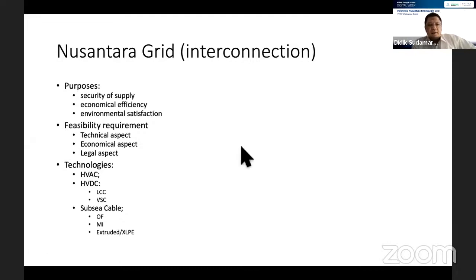The technology we have to focus on regarding this interconnection available in our system is about HVAC, high voltage AC current, and then HVDC. In HVDC we have two types, LCC and VSC, which I will explain later. For subsea cable, there are mainly two types: oil-filled and MI, which is mass impregnated paper, and the extruded cable, which is cross-linked polyethylene.